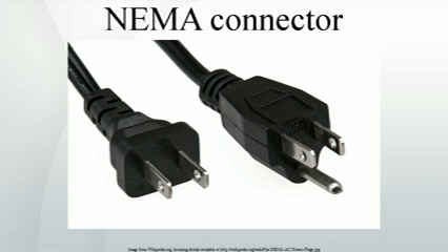NEMA 5. All NEMA 5 devices are three-wire grounding devices, hot, neutral, ground, rated for 125 V maximum, with the 5-15, 5-20 and 5-30 being grounded versions of the 1-15, 1-20 and 1-30, respectively. The addition is a 3/16 inch (4.763 mm) diameter round or U-shaped ground pin, 1/8 in (3.175 mm) longer than the power blades, so the device is grounded before the power is connected, and located below them by 1/4 in (6.35 mm) edge to edge or 15/32 in (11.91 mm) center to center.